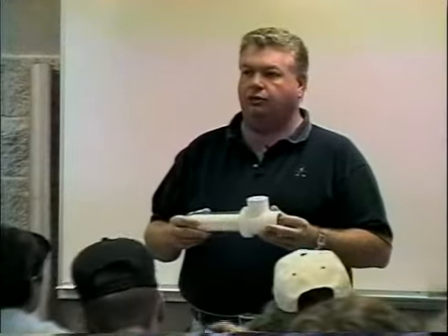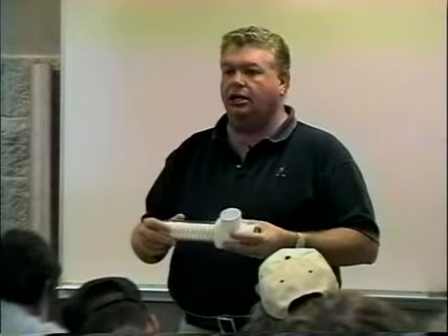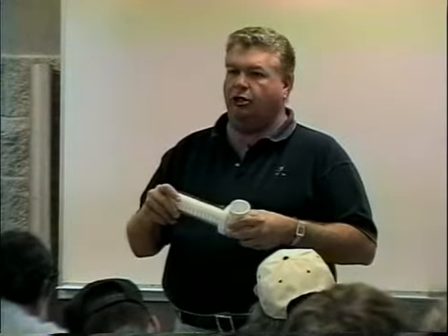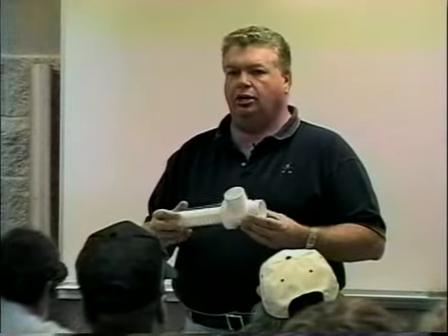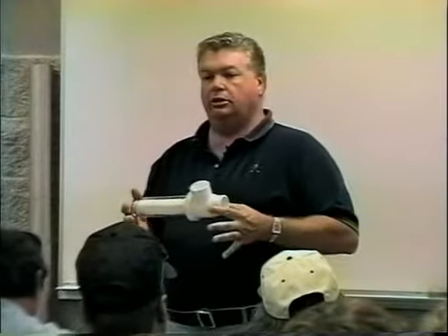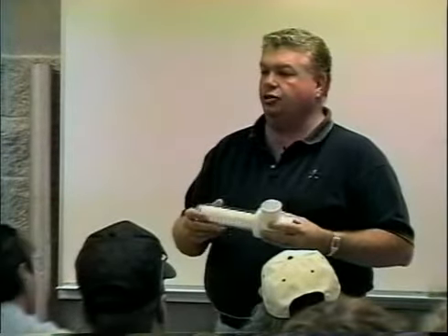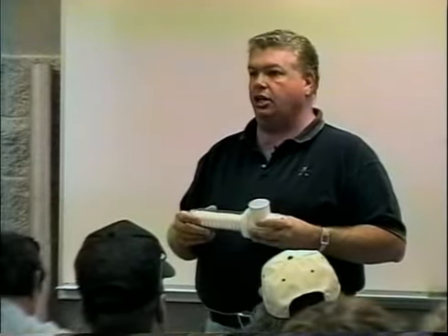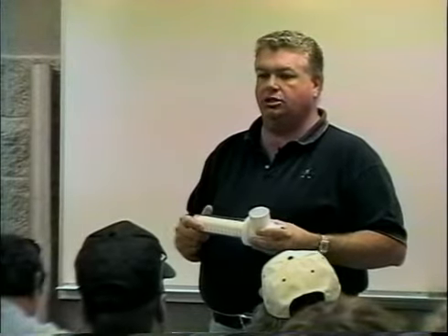Usually we monitor filtration by pressure drop. If we get a certain amount of pressure drop from the inlet to the outlet side, generally somewhere 8 to 10 psi drop in pressure, we know it's time to flush the filter. And on more sophisticated systems, it'll automatically do it. It's all set up. As soon as the pressure drops 8 psi, an automatic flush cycle comes on.